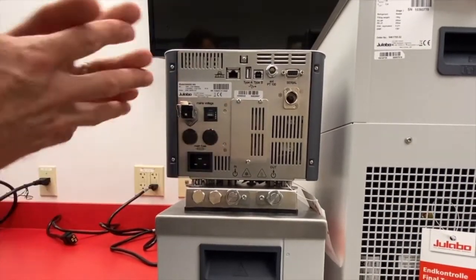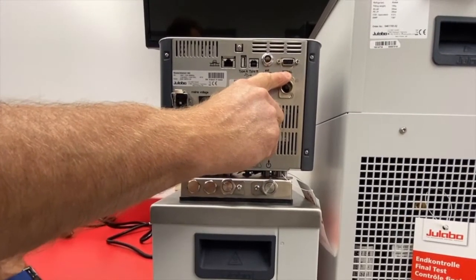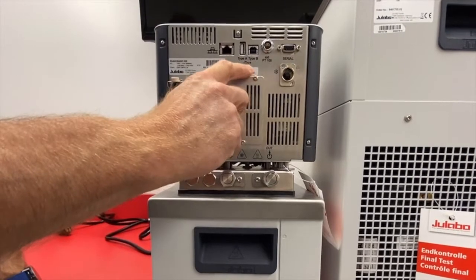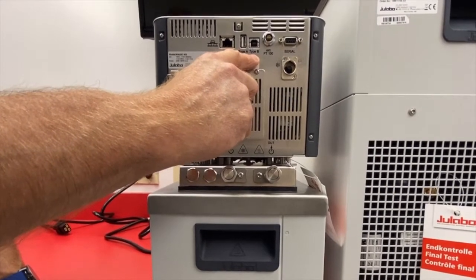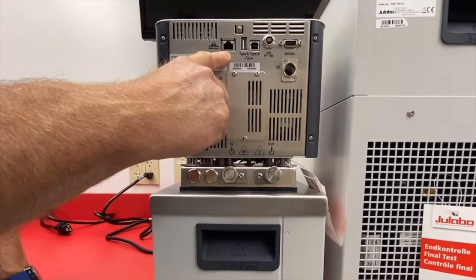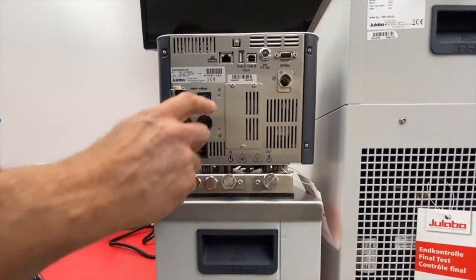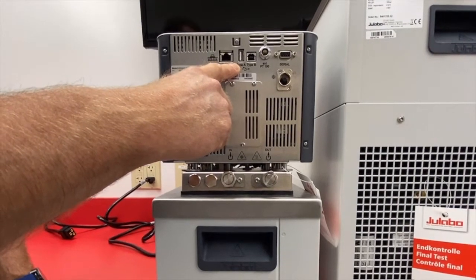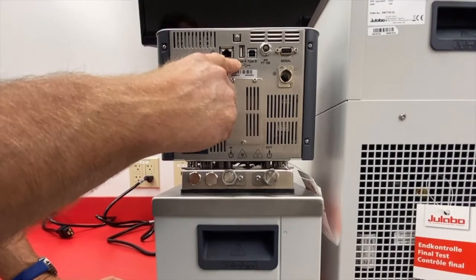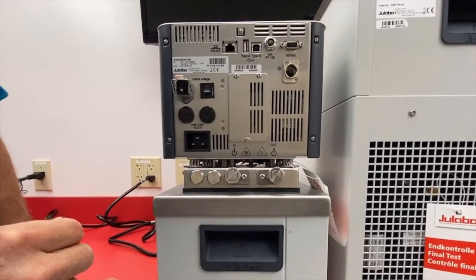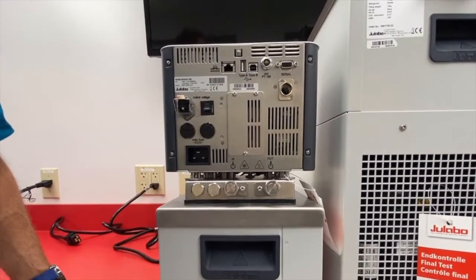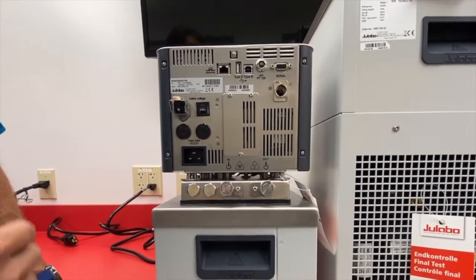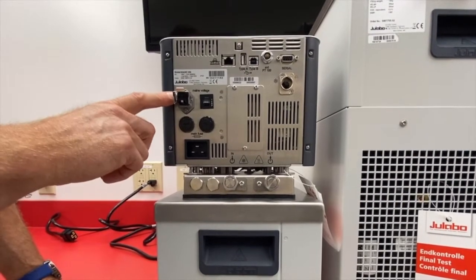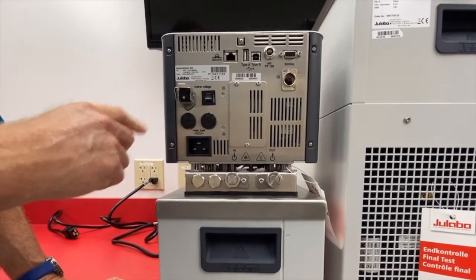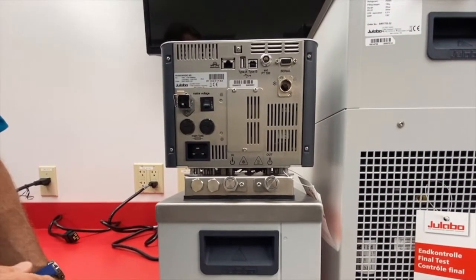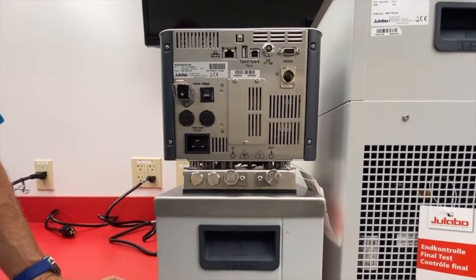All MAGIO models have the following on the back of them. You have a serial port for either RS-232 or RS-485, USB Type B for USB external communication, and an Ethernet connection. All MAGIOs incorporate the Modbus TCP/IP protocol. You also have the USB Type A for data logging, saving configuration and programs and transferring between MAGIOs, as well as black box service data storage. Obviously, then you have your external PT100 sensor port. And this slot here is reserved for the optional analog module if you need to control via voltage or current. And there is one Schuko outlet that is either 115 volt or 230 volt to control external devices such as inline solenoid valves or a cooling water valve, for example. And the MAGIO pump connections are M16 male.